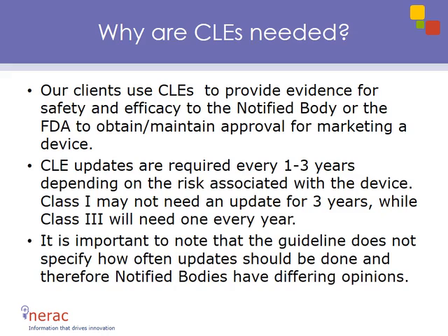A clinical literature evaluation is required for Class 1 sterile, all Class 1 non-sterile, all Class 2A, Class 2B, and Class 3 devices, and this is not likely to change with the new regulatory framework currently being debated in the European Union. What will change, however, is a broadening of the definition of medical device.